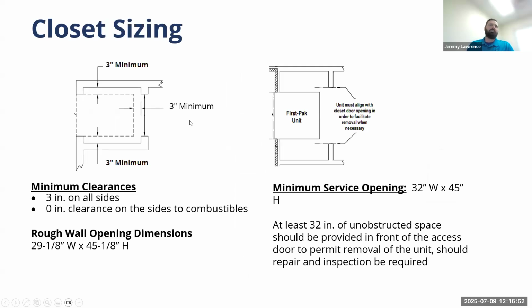Closet sizing. If we're doing a rear install sleeve, which is when we're pushing the unit straight into the sleeve as this, we only need 3 inches on either side. Very, very tight closet spaces. We know that condos and apartments and spaces are sold by the square footage these days, so we want to keep that livable square footage as much as possible. The First-Pak unit, which is that Magic Pack, Condo Pack competitive model, has a shorter, wider footprint, so it needs a wider closet space as well. If you were doing a side install and the wall was here and the door was on the side here, we would also need a larger closet, approximately 3 inches on this side, 12 inches on the front, and 12 inches on this side, because the unit actually has to get up onto the sleeve, then turn before it can push in and seal to the sleeve. So more space is needed.